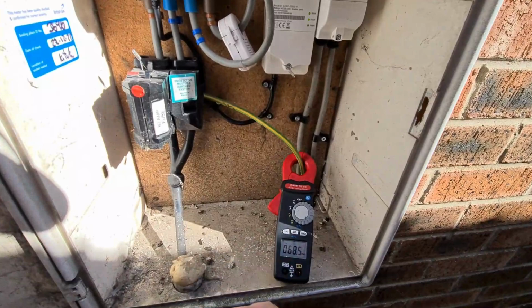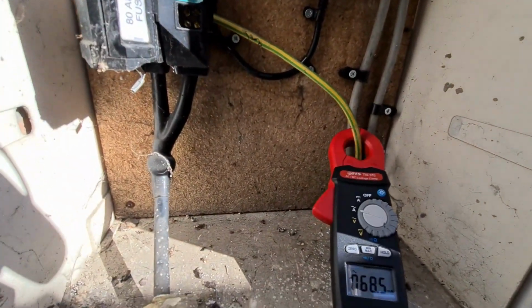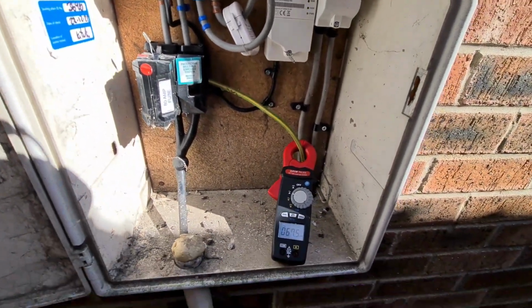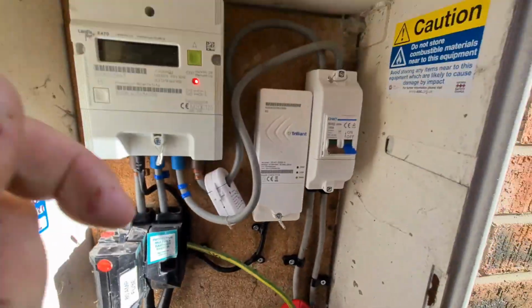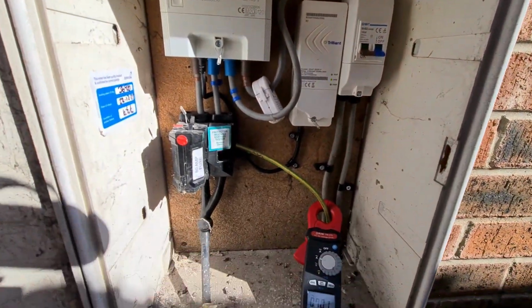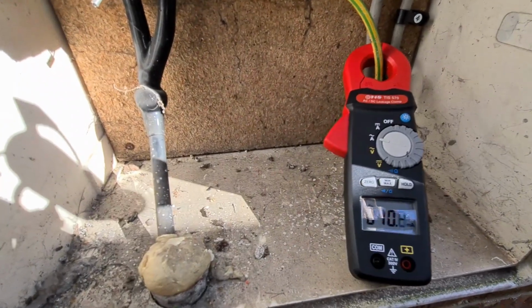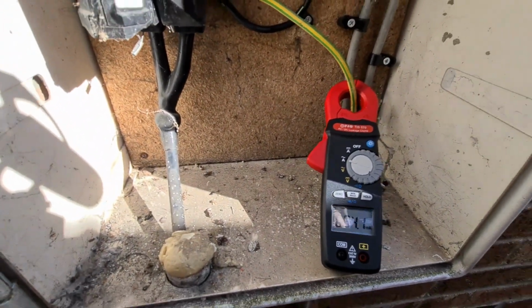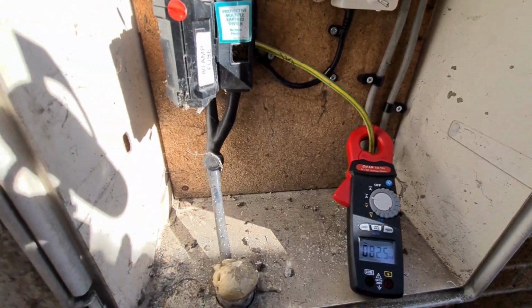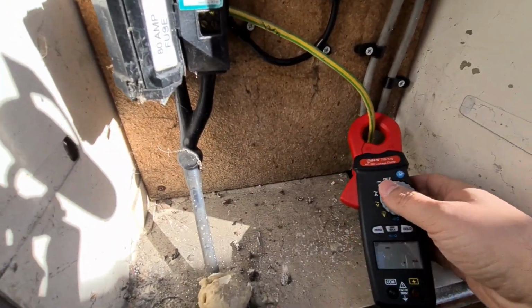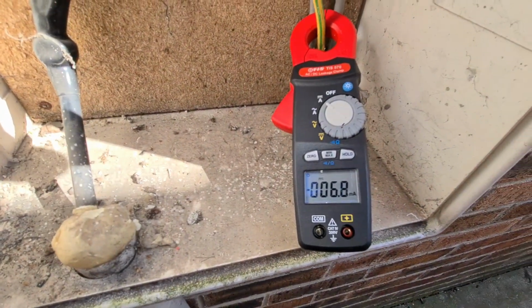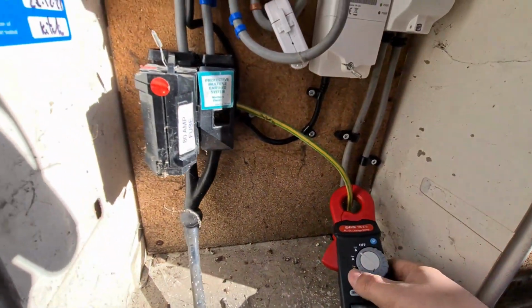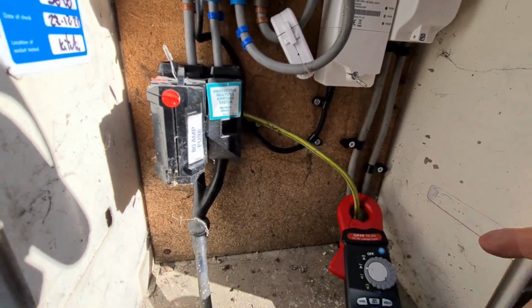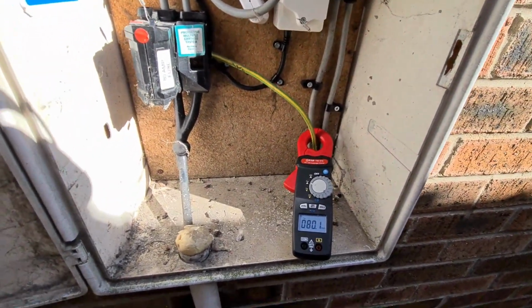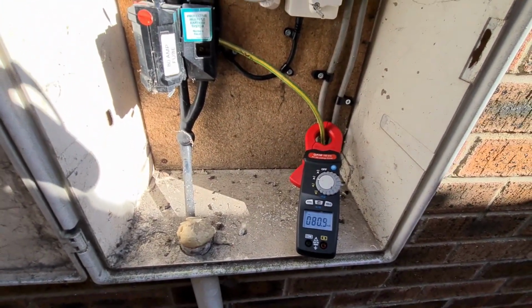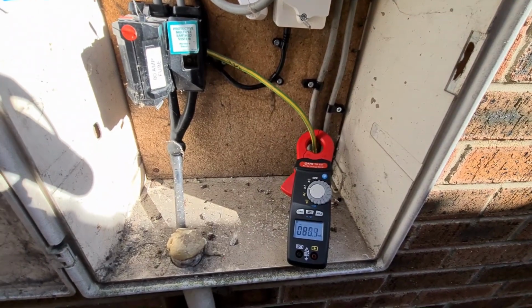Rather interestingly, we've got around 60 odd milliamps of leakage current floating around on the earthing system. Obviously my installation's off, so that's coming from somewhere else - it can't possibly come in on this installation, and that's on the AC scale. If I move that over onto DC as well, you see there's a little bit of DC leakage current too. It works better if you're between the line and neutrals together, but I don't have access to them while the system's switched off, so we can only take that measurement through the earthing conductor.